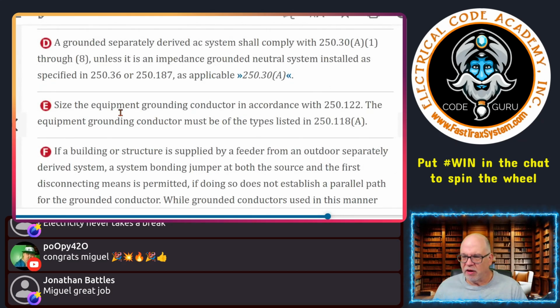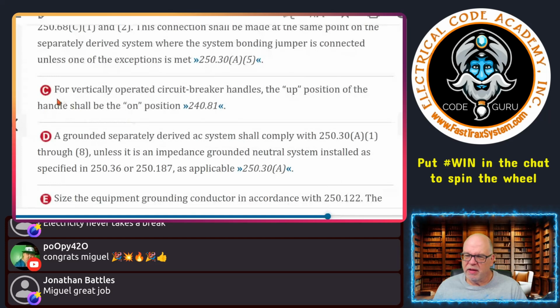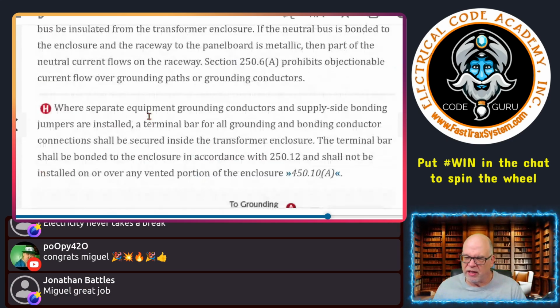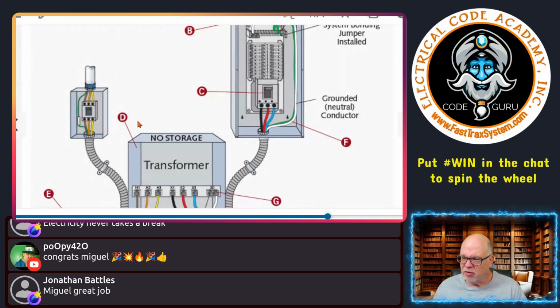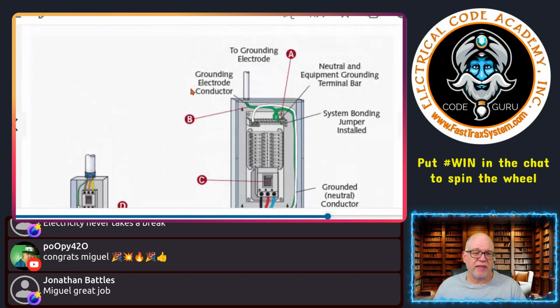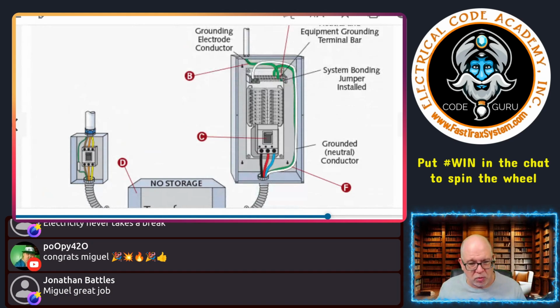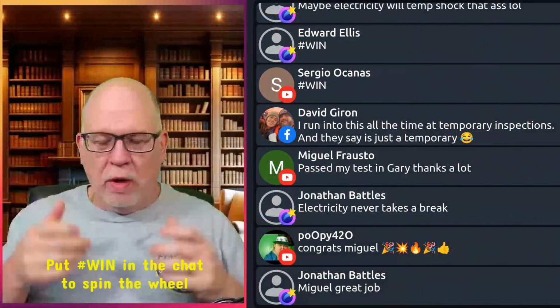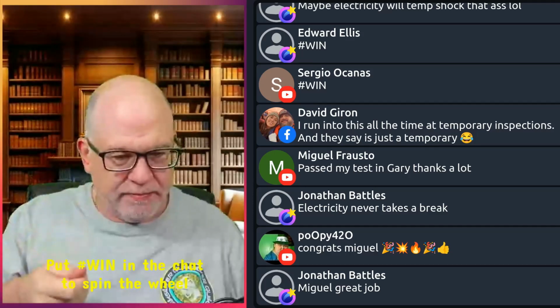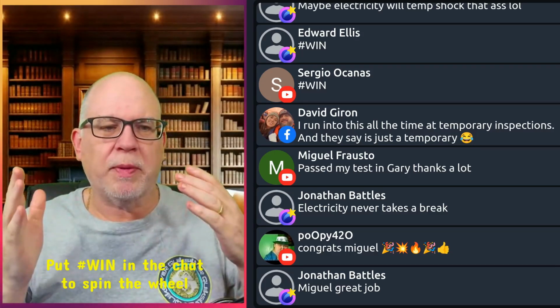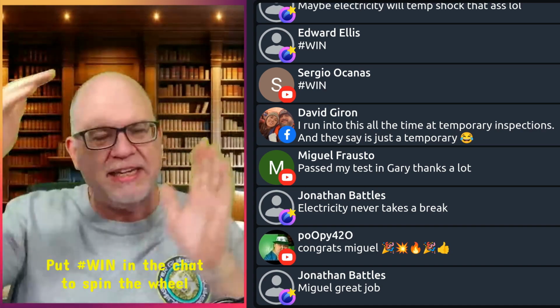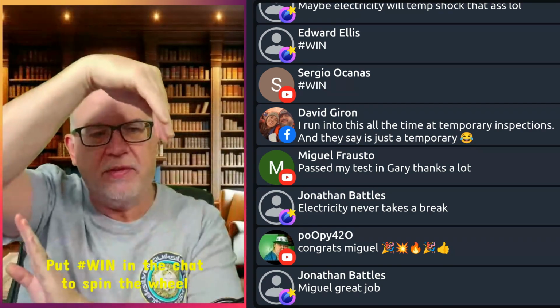All right, so let's see here. Okay, so that was, say now, C, for vertically operated circuit breaker handles in the up position. Okay, we don't really need to look at that, but that's 240.81. That is basically referring over here. And obviously, the only important thing I'll bring up about this is orientation of panel boards, right? So the NEC only cares when it's a circuit breaker that is operated vertically. If it's horizontally, doesn't matter, and typically those panels will be clear that it could be upside down or either way, up or flipped, okay?